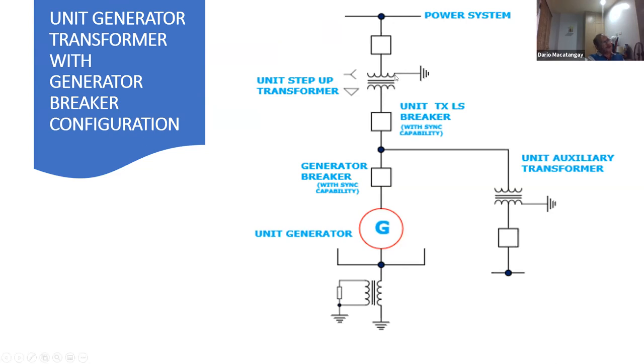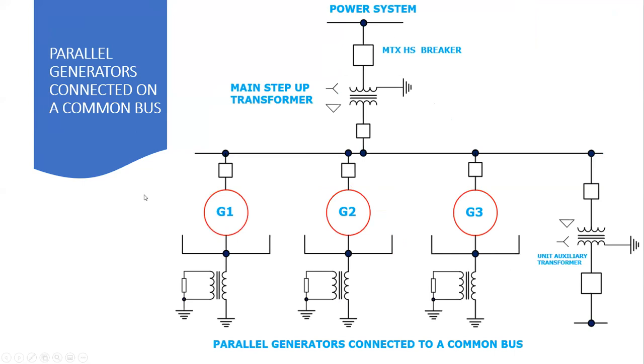So if you have a fault on the transformer, the generator powers the load, and after correction of the fault in the transformer, you can synchronize here. Or this one here, of course you have to trip this one, but you have to close this one first, I'm sorry, and then synchronize here, okay? So far so good? Okay, good, thank you.